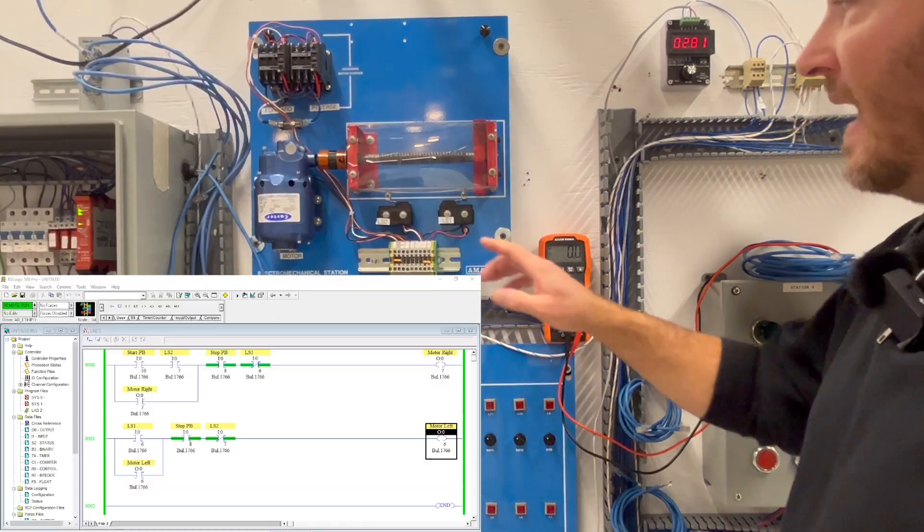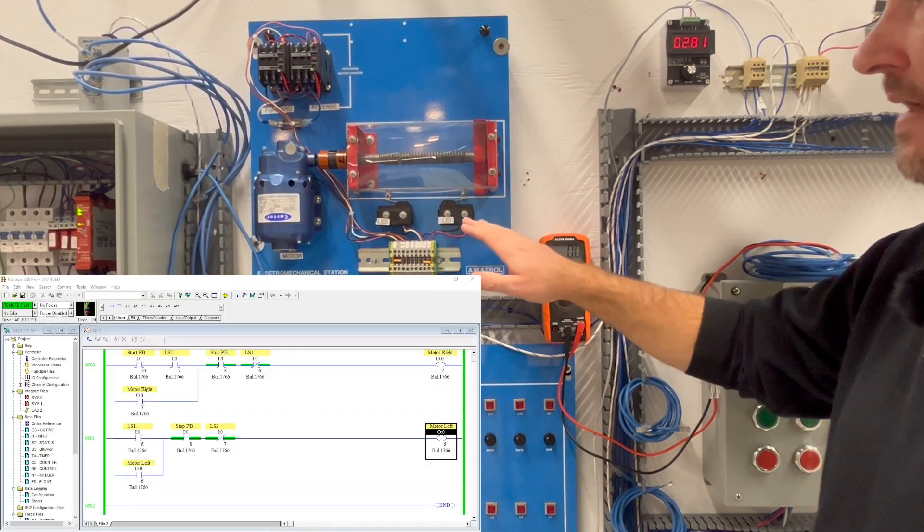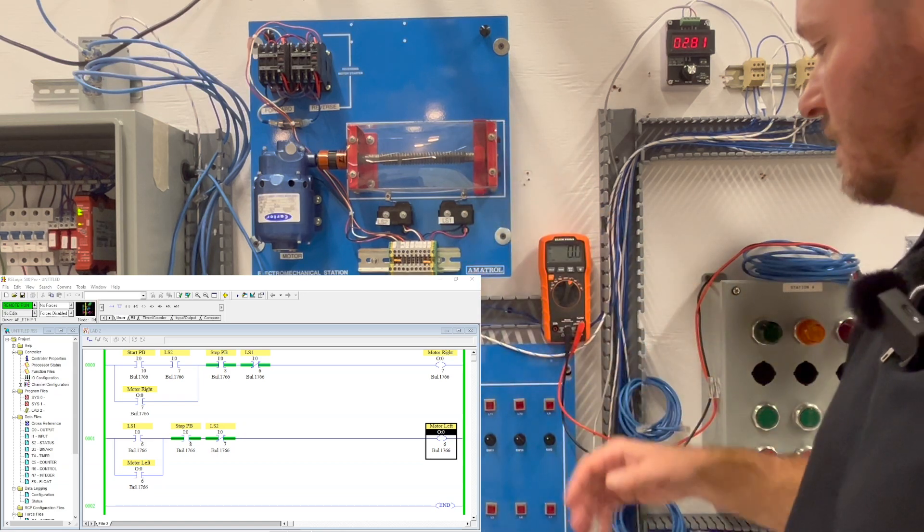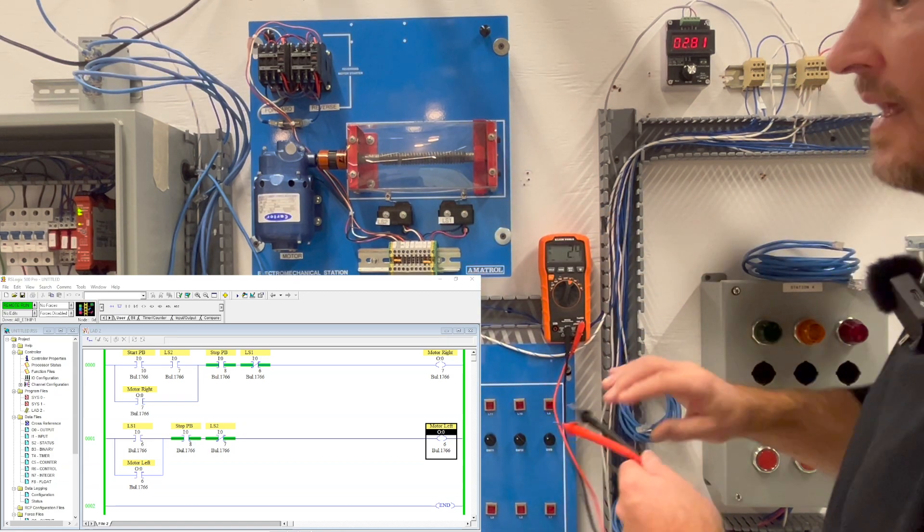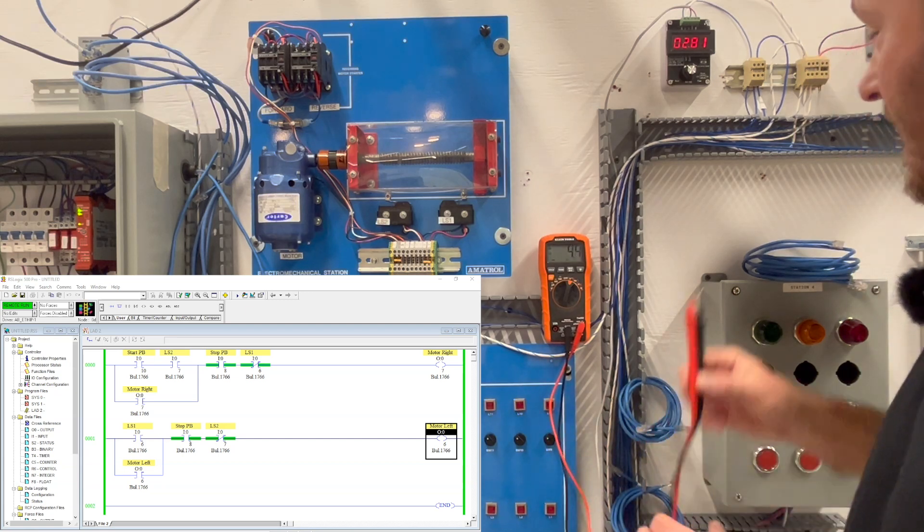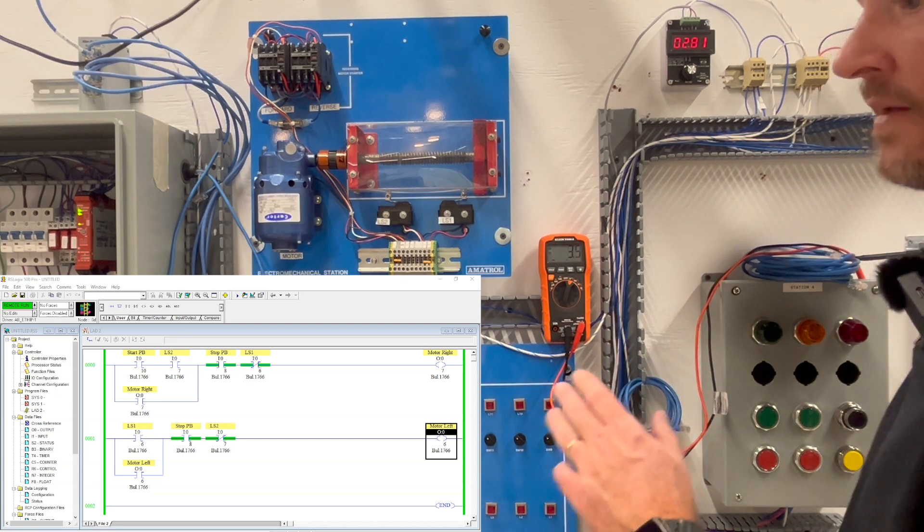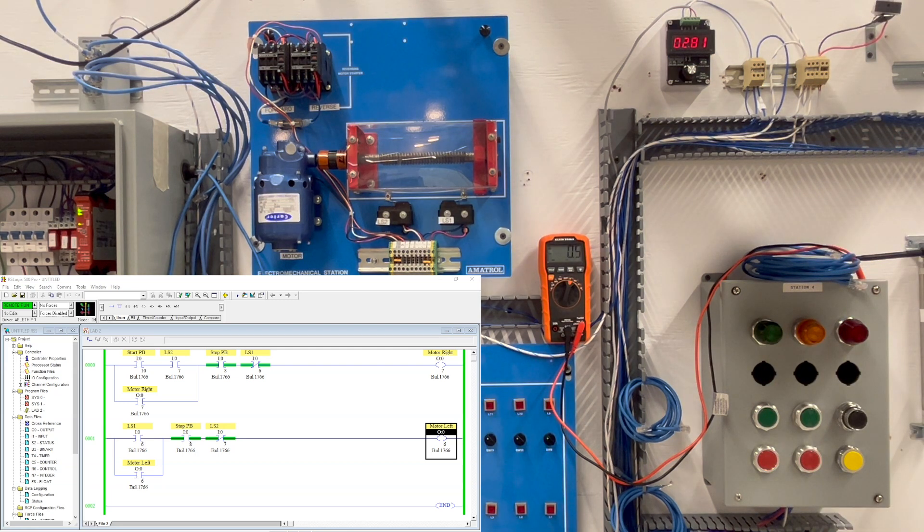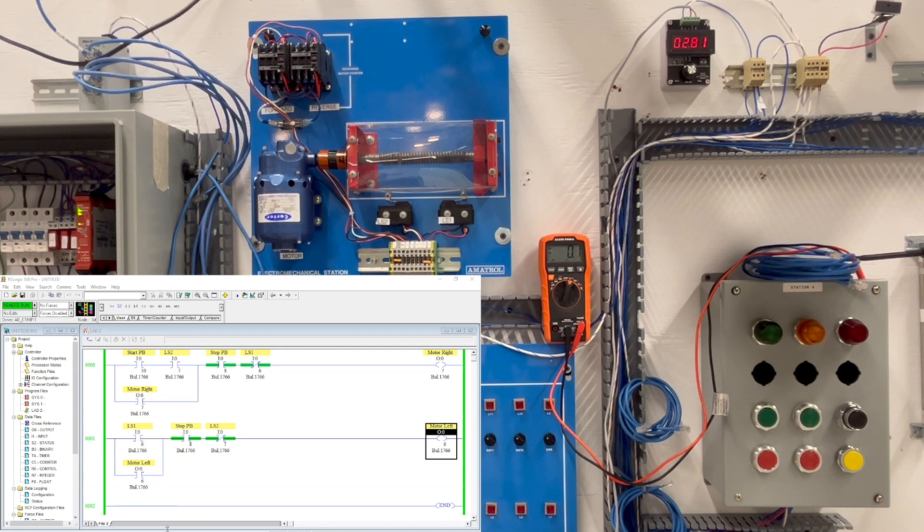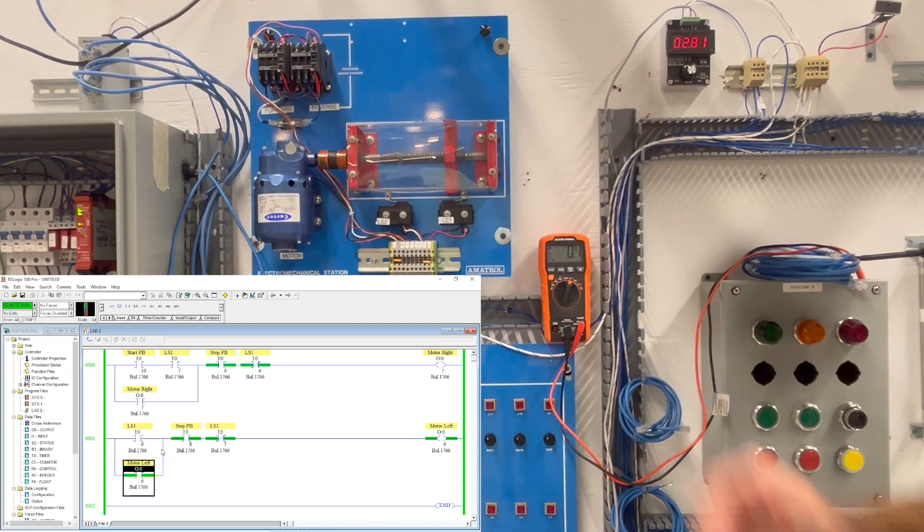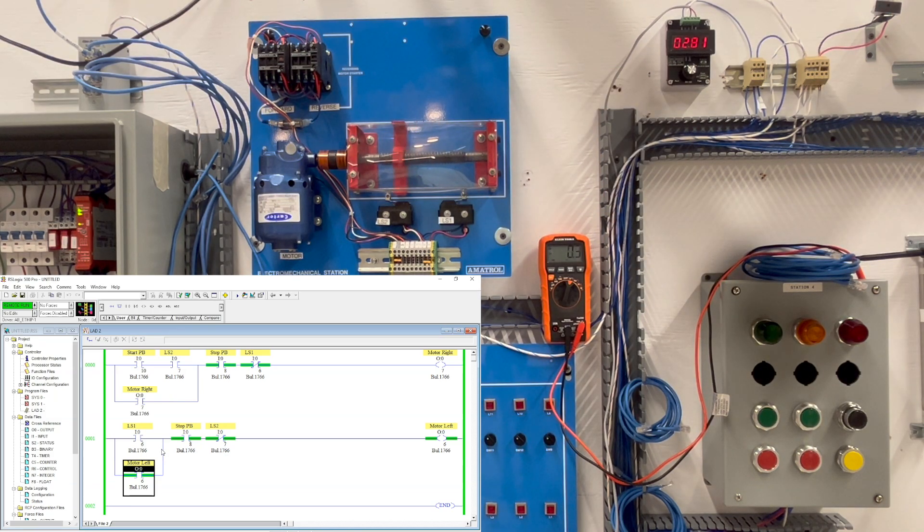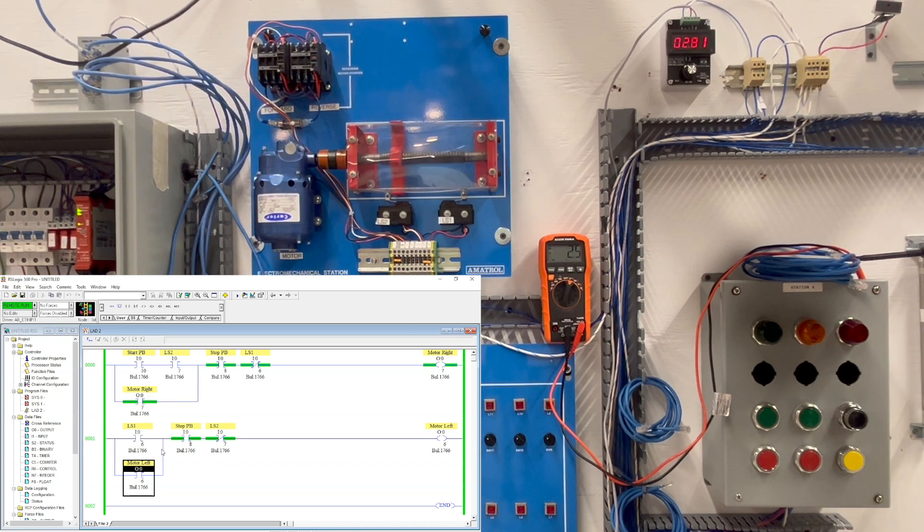So now I don't want to come in here and activate this because I don't want the machine to start running, so what I can do is I'm going to go ahead and override the machine here in the PLC to make sure that this thing will track back. So I want this to go motor left so in this case I'll just right click, toggle bit, shift this over. Allow this to run, it stops, I'll activate it.